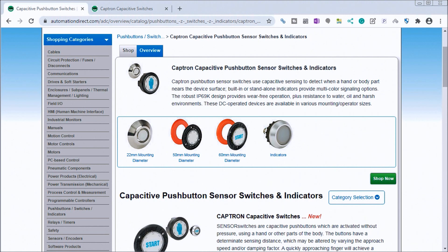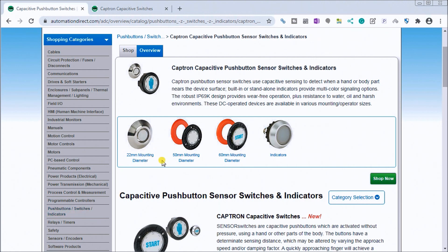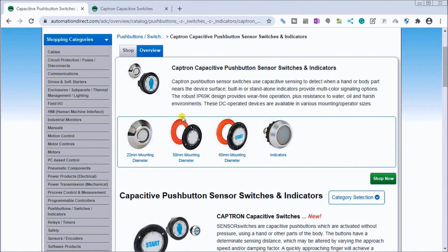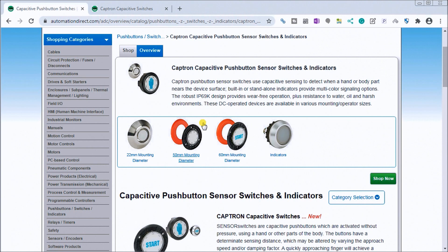So the Captron capacitive switch actually comes in three different models: we have the 22 millimeter, we have a 50 millimeter, and we have a 60 millimeter. And you can see with the diagram here you can have colored indication on each one of these switches that we can place over top, so they come in several different colors. And all of these switches are PNP normally open, and we also have indicator lights that also come 22 millimeters in diameter for pilot lights in our panel.